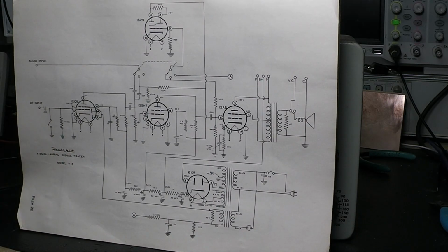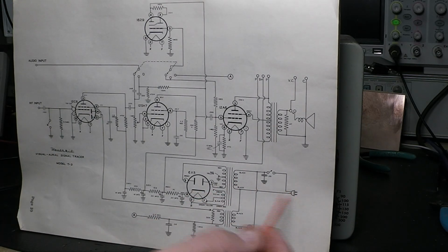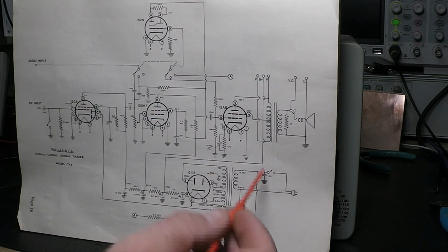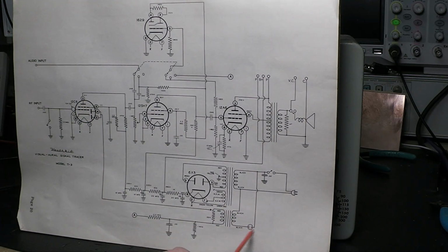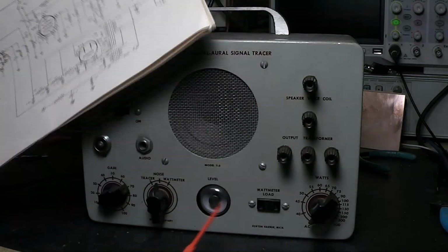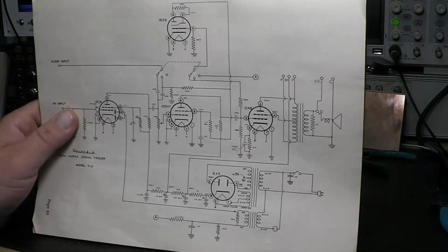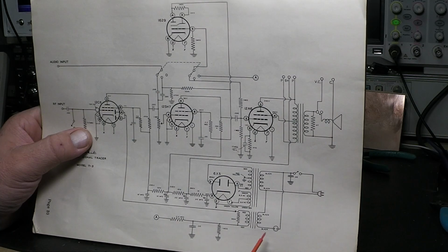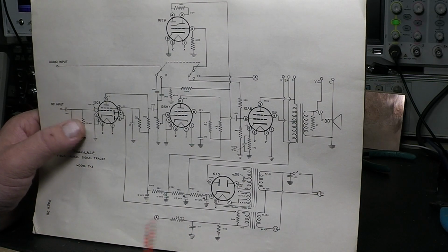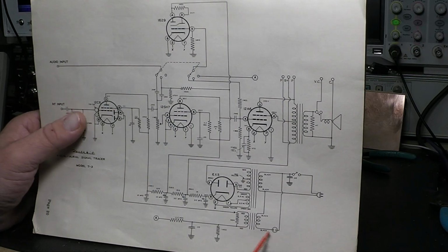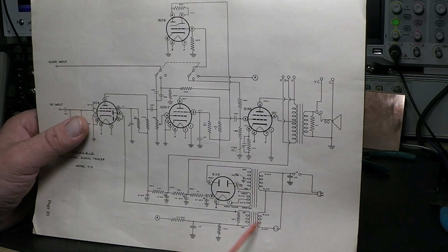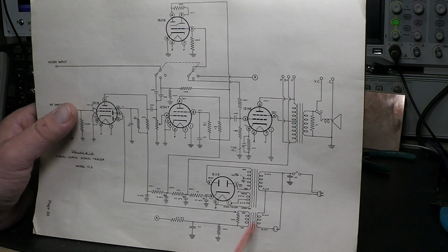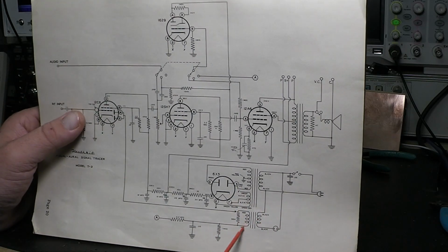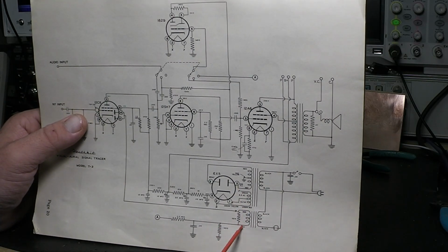Getting back to the watt meter, you get your line cord coming in here. One side's tied to one side of this transformer. The other side goes through this plug to this side of the transformer, and that's that plug right here on the face of the unit. So when you plug in a load here, depending on how much current it draws, how much load is on it, it's going to depend on how much this transformer is going to transform on this other side and impose a voltage over here.